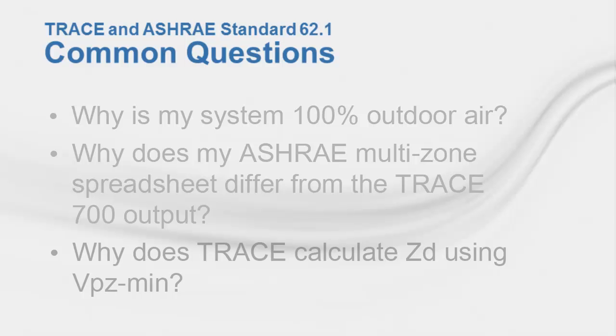We also often get the question of why TRACE calculates Z sub D using minimum stop air flows. In the standard, it defines V sub PZ for VAV systems as the minimum expected primary airflow for design purposes. TRACE is being conservative in its assumption that the minimum expected airflow in the critical zone at design conditions equals V sub PZ min. The airflow rates using the ventilation rate procedure in 62.1 should be considered minimum outdoor airflow rates, so TRACE uses the minimum stop airflow to ensure the proper amount of ventilation is supplied to meet the critical zone even in worst-case conditions—when system airflow is at design rates and the critical zone airflow is at minimum stop.